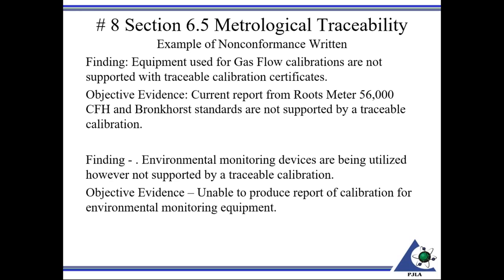Another example would be perhaps your environmental devices where you capture and monitor environmental conditions. If they're reported to the customer and if they're a contributor to your uncertainty, then they would also need to be traceable. So here's an example of a finding that was written where in this particular case, those devices were being used and incorporated into the results. However, there was no objective evidence produced that they were even calibrated, let alone calibrated by a traceable source.